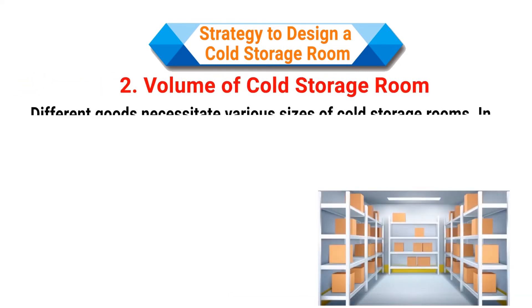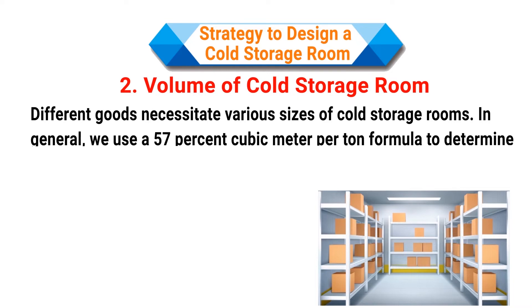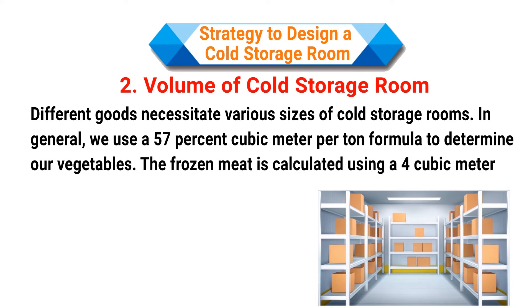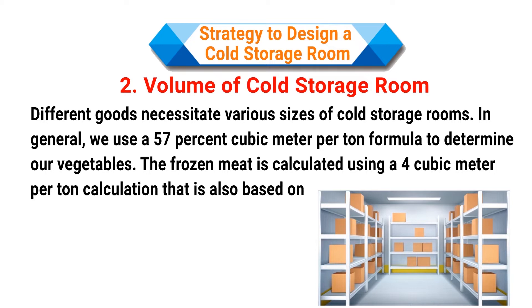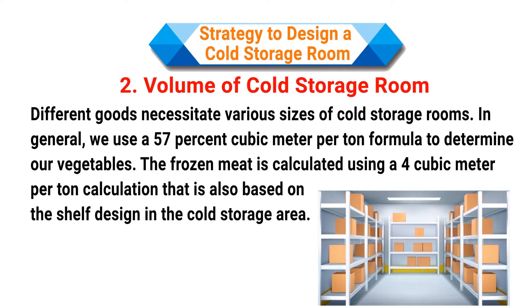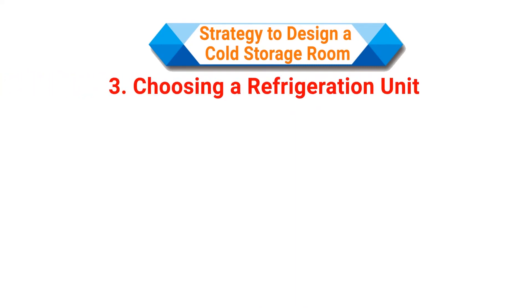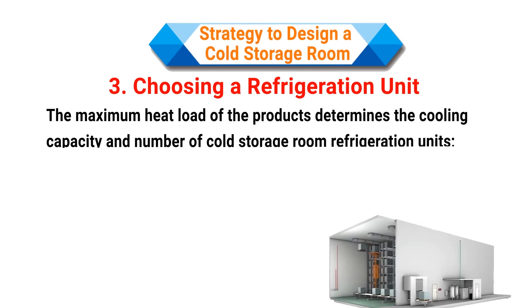Different goods necessitate various sizes of cold storage rooms. In general, we use a 5–7 cubic meter per ton formula to determine sizing for vegetables. Frozen meat is calculated using 4 cubic meters per ton, which is also based on the shelf design in the cold storage area.